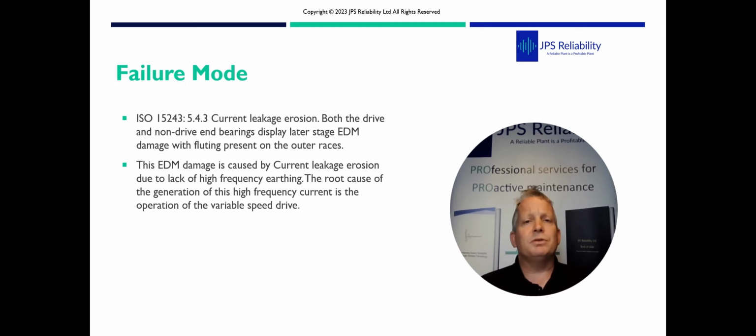Or is the root cause all the way back to the electrical engineer who was designing the system, who didn't take into account or understand the effects of the high switching current in the drive? Is that the root cause failure at the design stage? Not just the drive, because the drive caused it. The drive caused it because of the lack of high frequency earthing. So it's a debate on the failure mode or the root cause. Technically it's current leakage erosion, but it's due to the lack of high frequency earthing, which comes back to the design stage, not taken into consideration in the design or the retrofit.